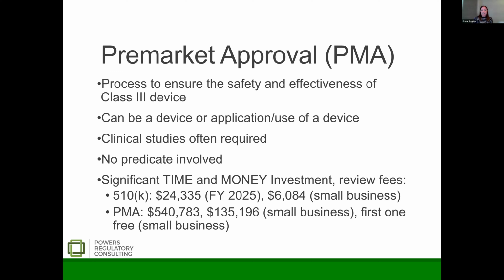I often get asked about what's the difference between PMA and 510K. Well, it's definitely reflected in the FDA user fees. So the cost for a 510K to be reviewed is $24,000 for a larger company. That's the fiscal year 2025, 6,000 for a small business. Small business with FDA means you have to have a tax return for your company showing that your revenue is under $30 million, which is the case for most people that I work with. So we do the small business fees routinely, but you do have to go through a process with FDA to be designated a small business to get that discount. And so with a PMA, you can see $500,000 review for a bigger company. That's reflective of how much documentation and effort it takes on the FDA side to be able to do that review.